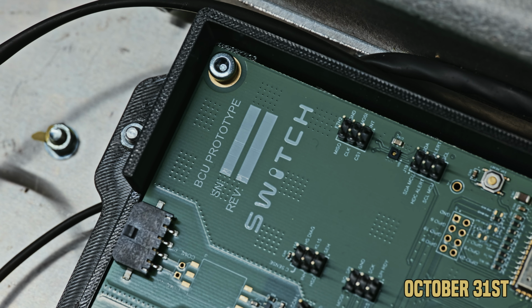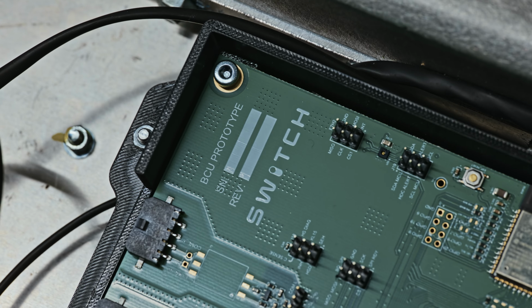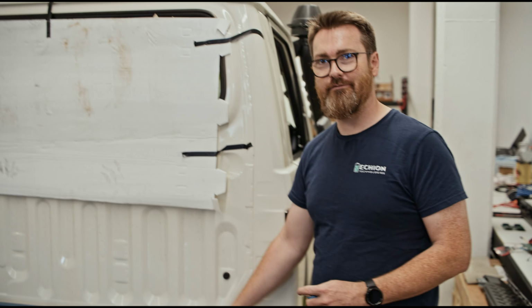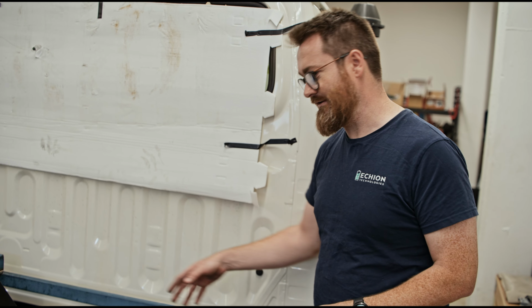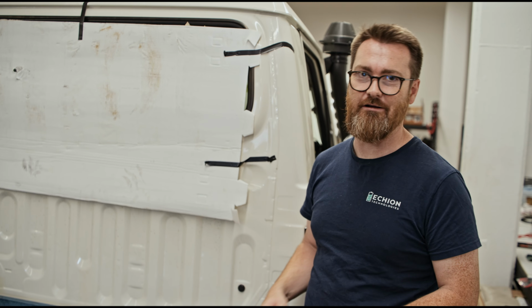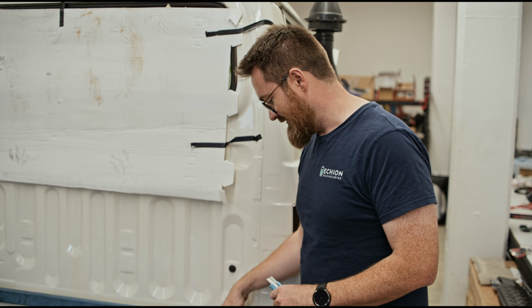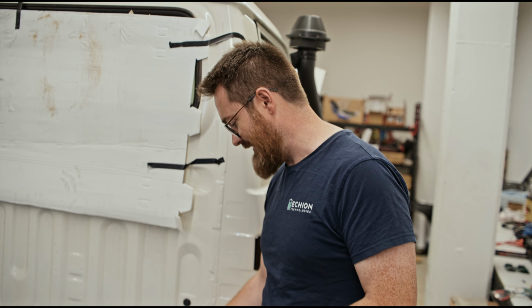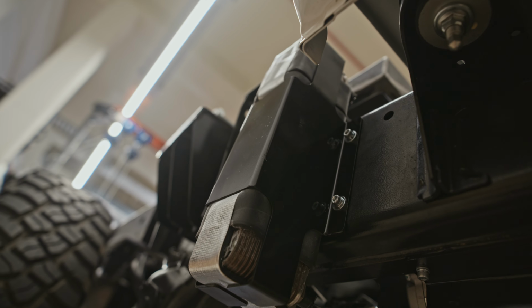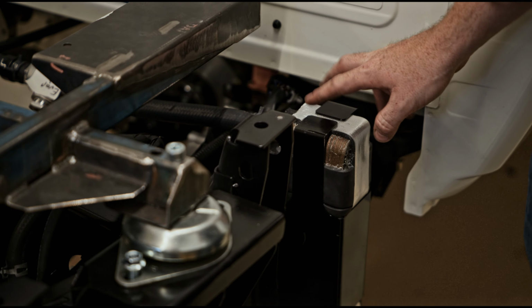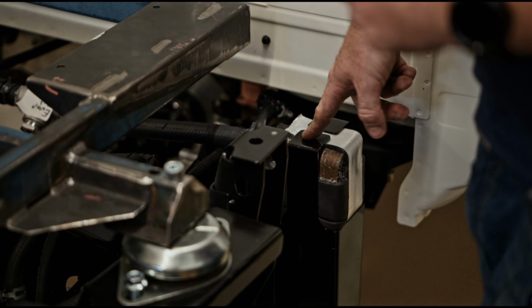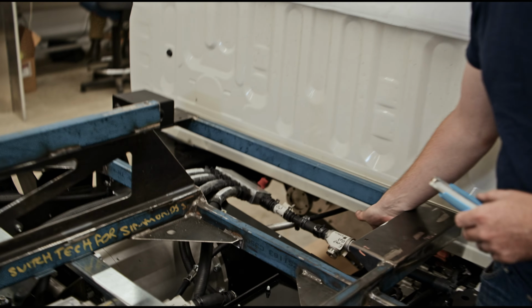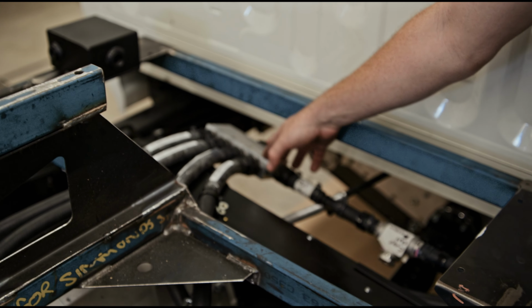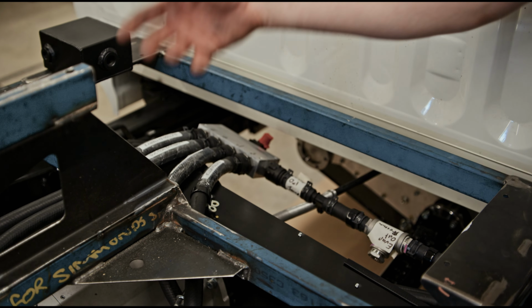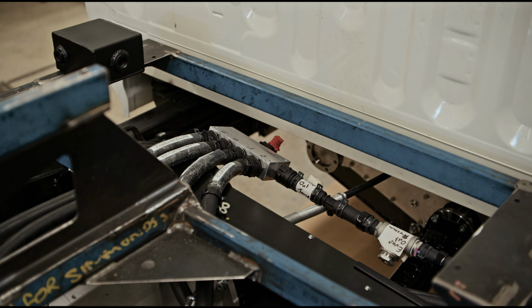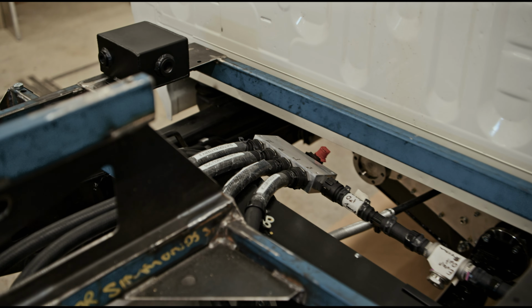As we've discussed before, it's a refrigerative cooling system, with a water loop around all the actual components. We've got the evaporator installed now, which is like the heat exchanger between the two sides of the system. That feeds cold water into this manifold, and then we've got 4 separate coolant loops and 4 separate pumps.